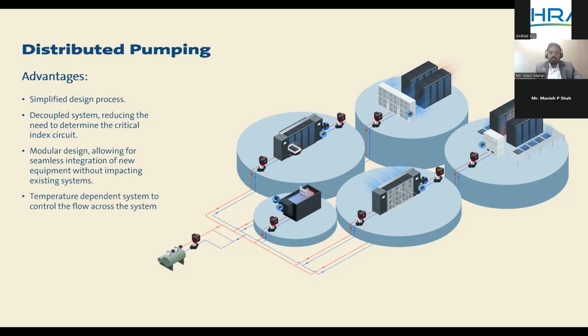And as I said, the conventional system operates based on pressure. We monitor the differential pressure across the critical load or furthest load, and based on that feedback, we try to modulate the flow, which is distributed across the various loads connected in the system. Is that the right way of doing it? Yes, but there are better ways of doing it. The actual flow has to be controlled by understanding the temperature need of each load, and that's where we are moving with distributed pumping.